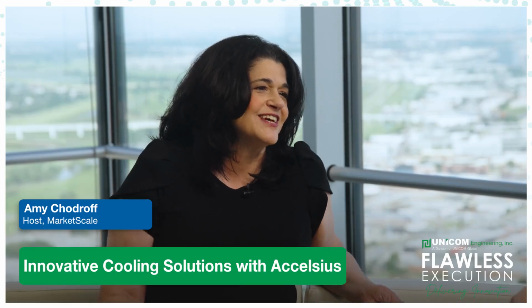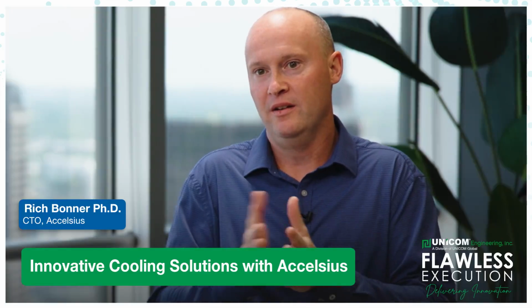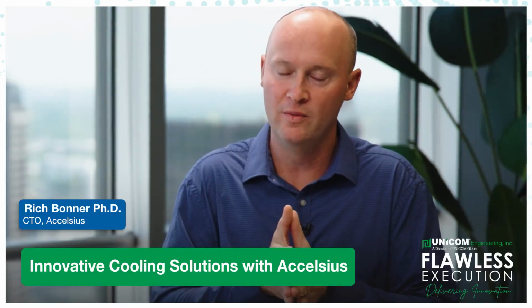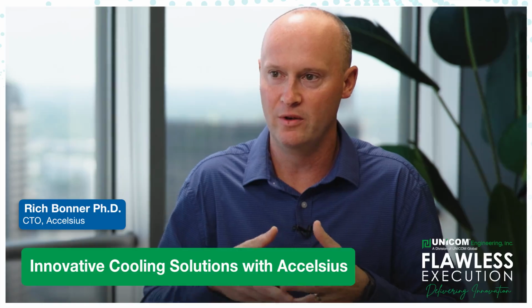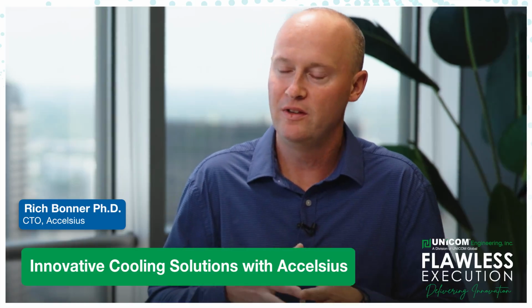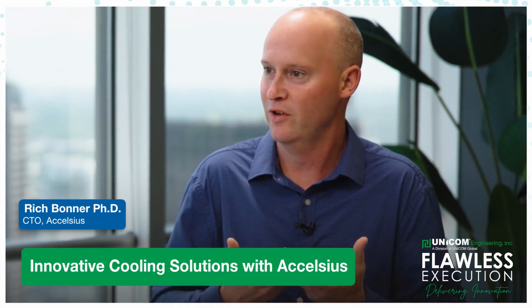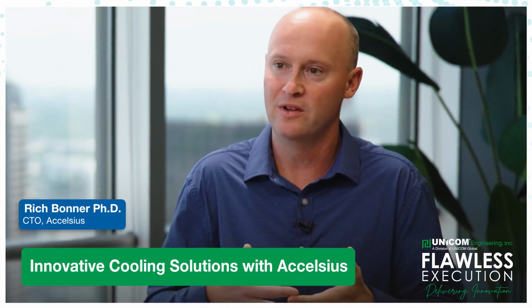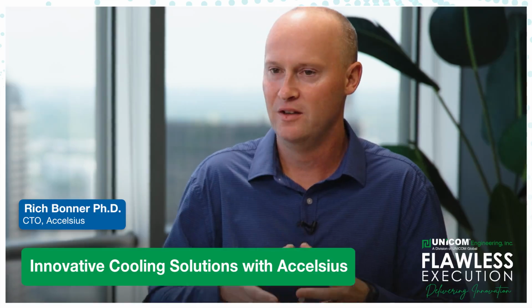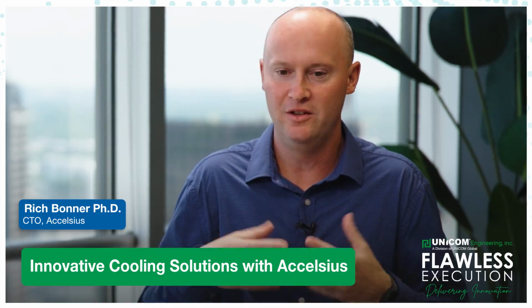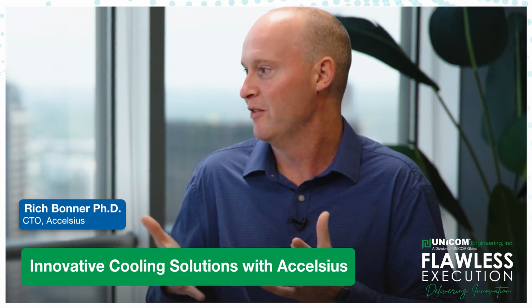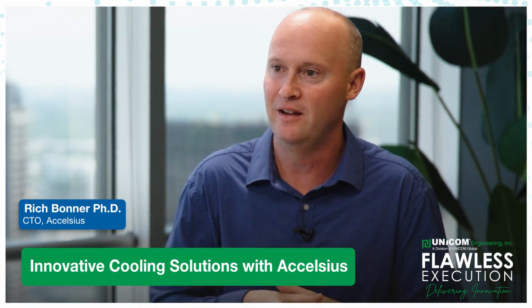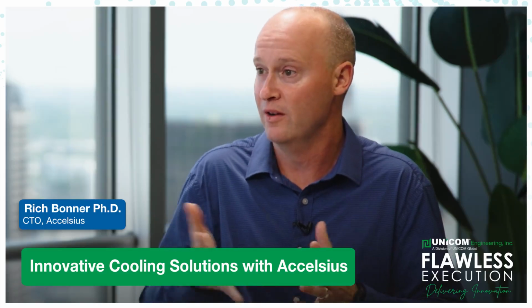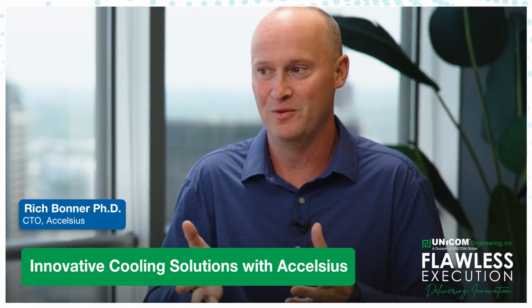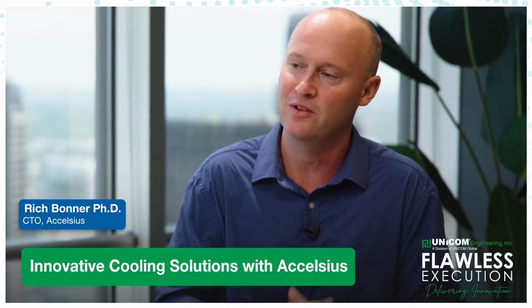And how is this different than other technology that's out there? Well, it's different in terms of the physics I talked about and the performance. It's also different in terms of some other reliability-based benefits. One of the unique things about two-phase cooling is it allows us to use refrigerant-based working fluids, and refrigerant-based working fluids do not conduct electricity at all. So if there's a leak or any issue with your system, you don't have to worry about destroying several million dollars of IT equipment in some of these AI racks. Whereas if you're using water or other solutions, you have to worry about that, and it does cause lost sleep. So that's one of those unique advantages.